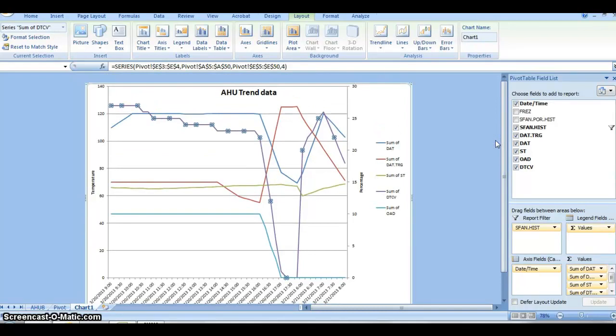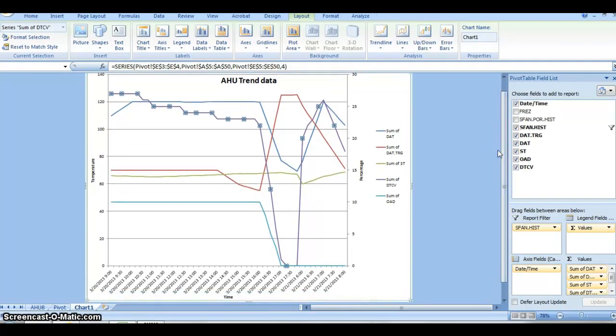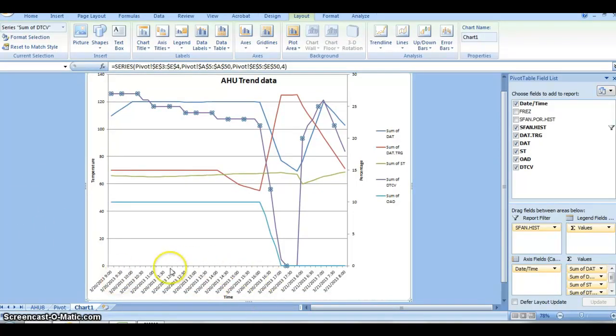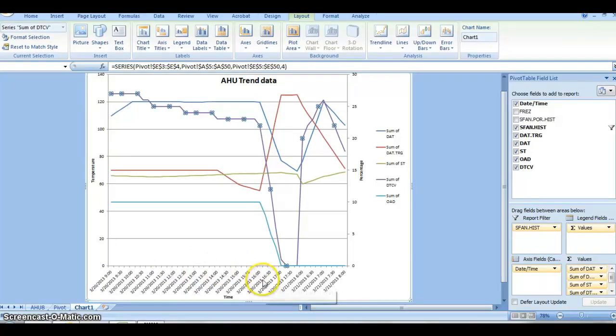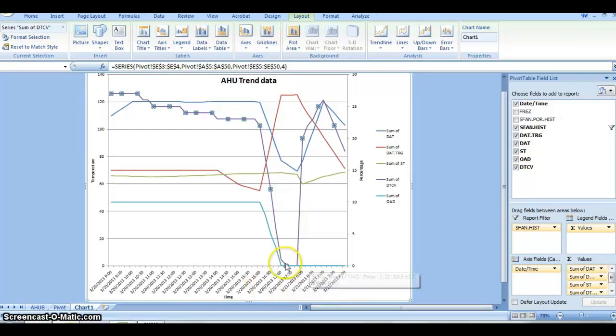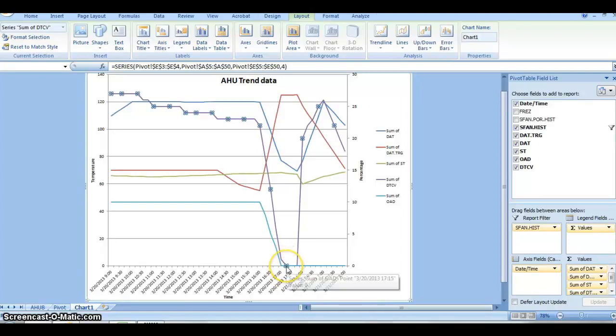Now we have everything labeled and it's easy to read. We can see what time the supply fan is being run, which is down here at the primary axis. We know the fan kicks on around 9 a.m. and it turns off around 5:30 in the evening, which is good because it's a school and that's when everybody starts leaving to go home.